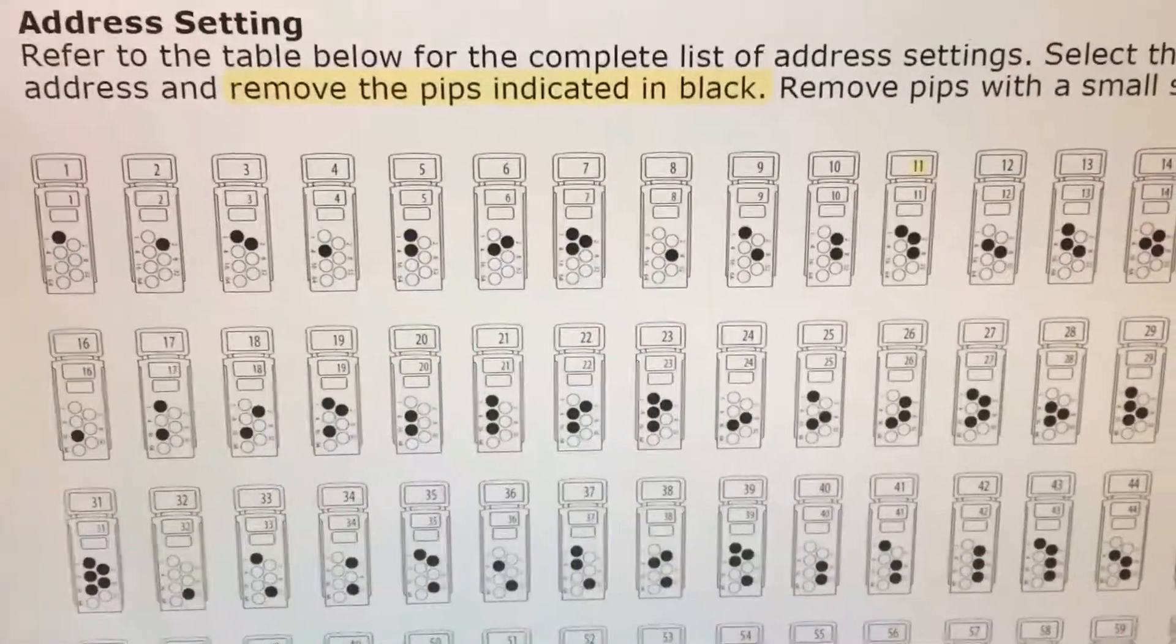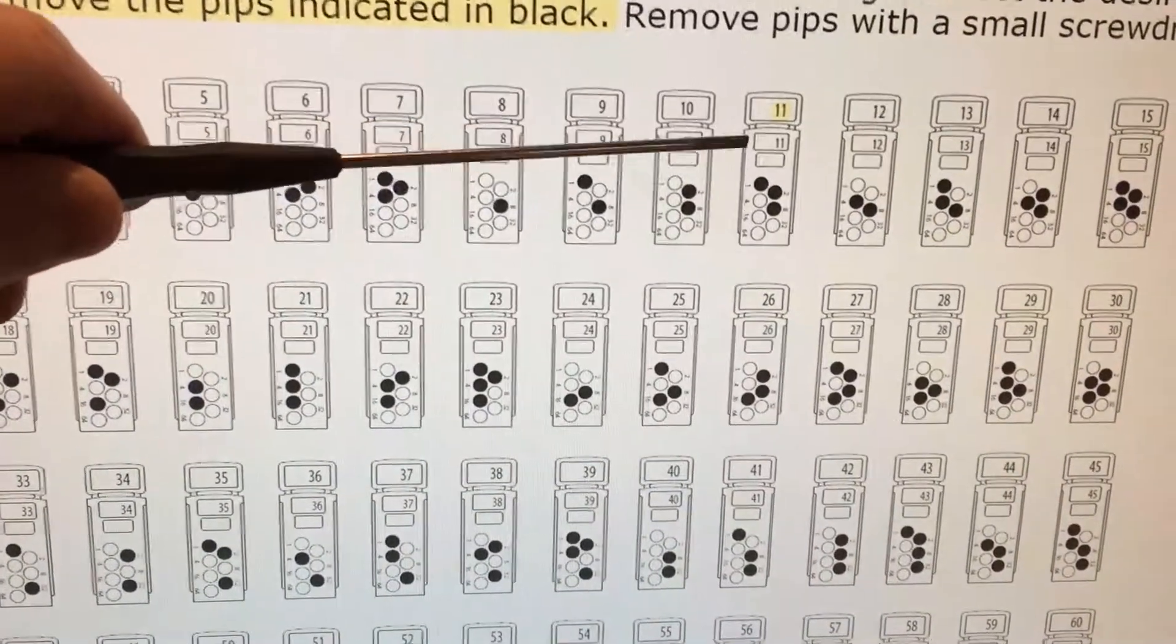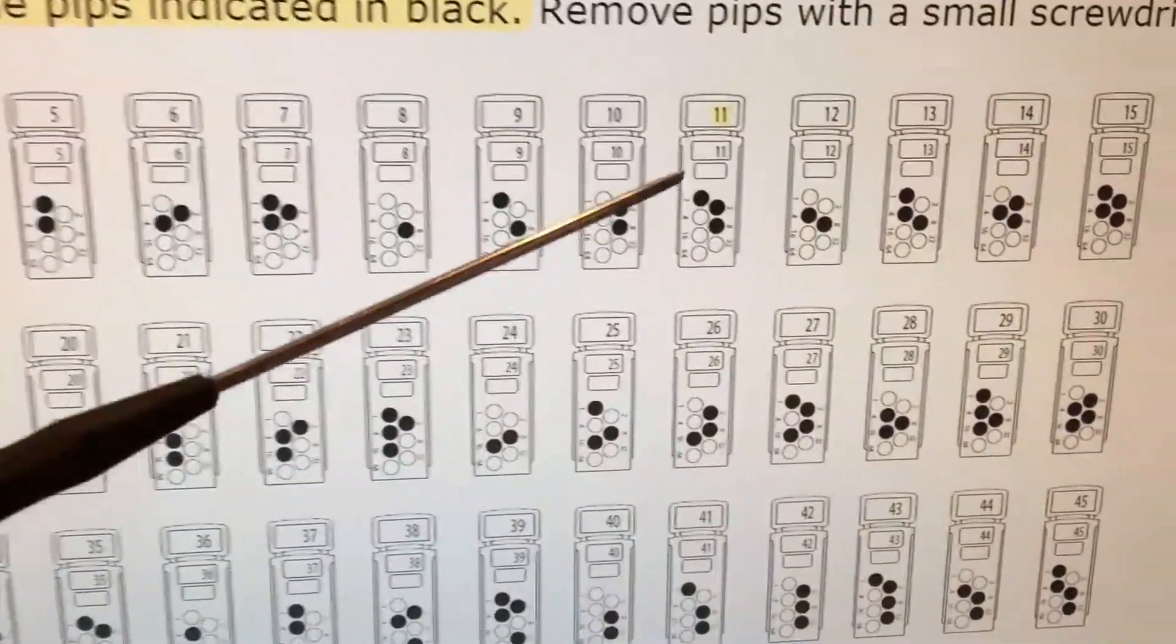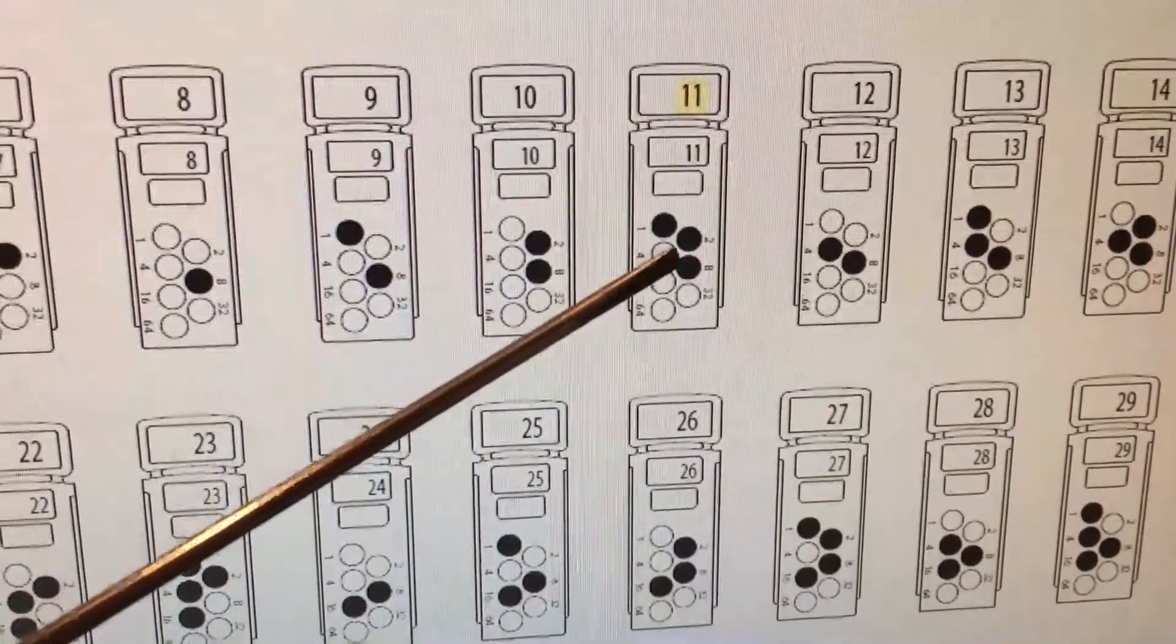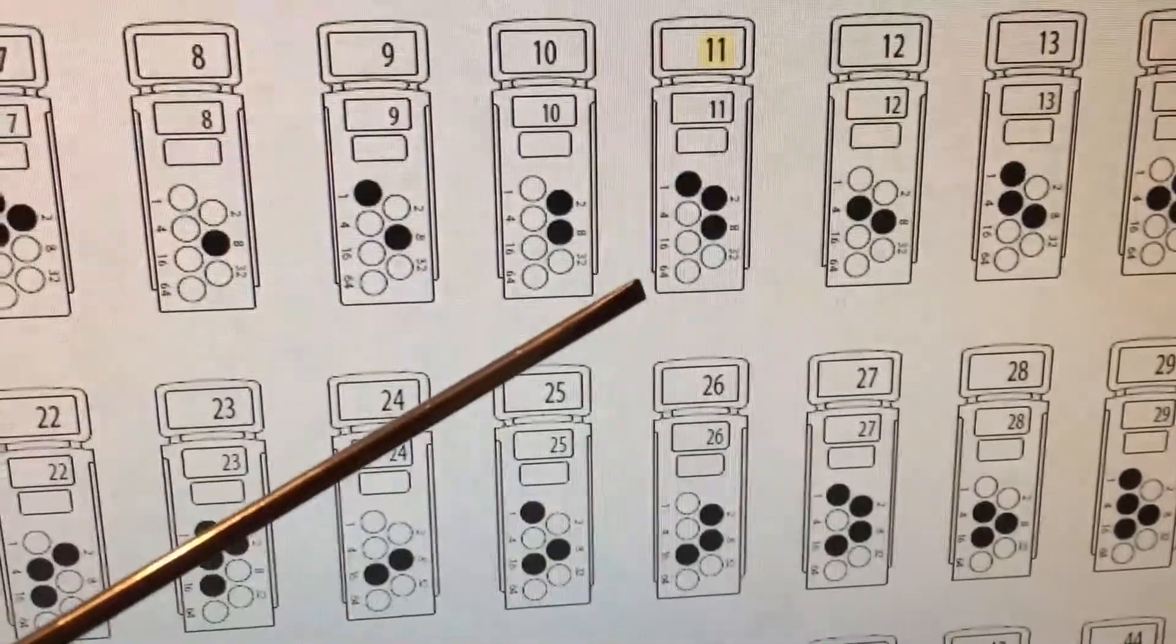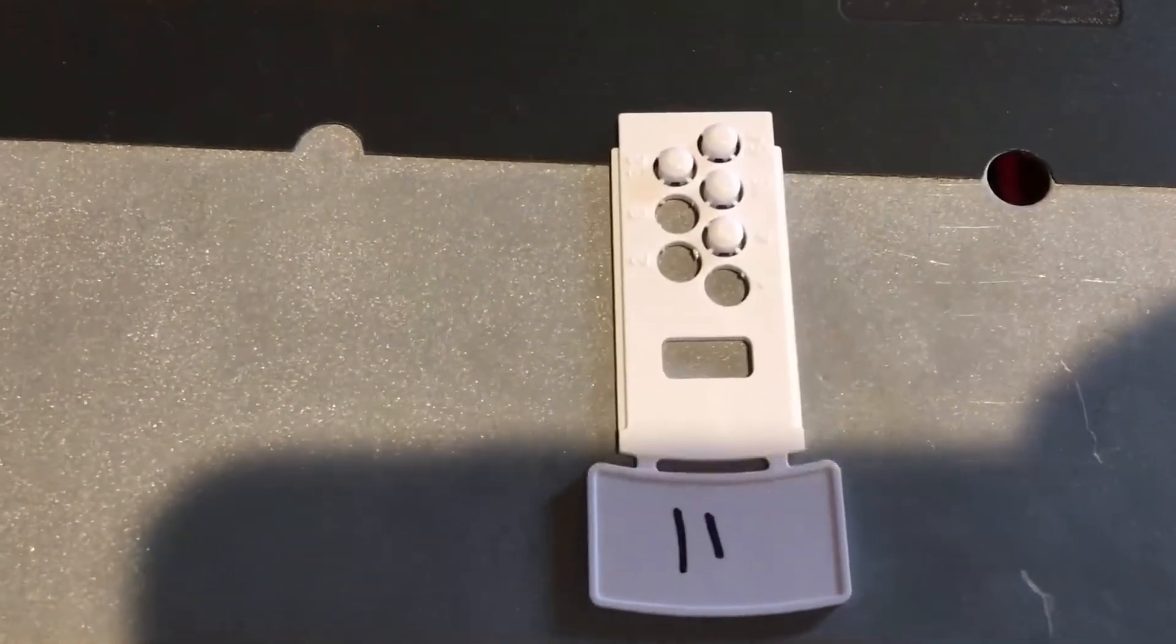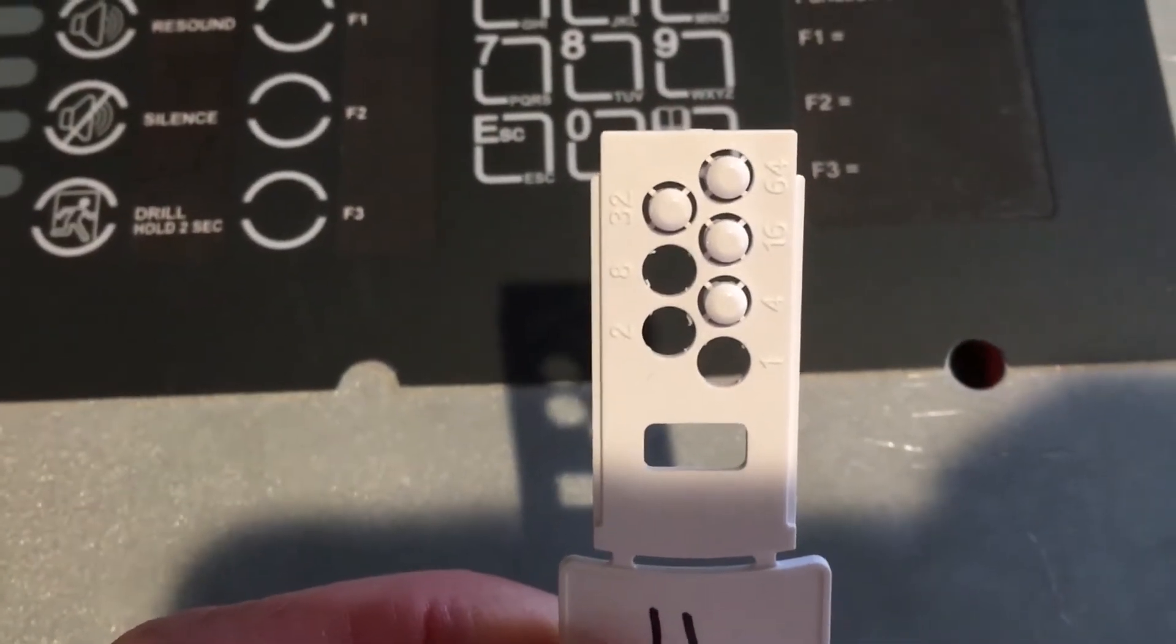Our next item is going to be a smoke detector and that's going to be inserted into a base. You slide out the addressable card and as it says up here, remove the pips indicated in black and that sets the address. This device is going to be address number eleven. Each of these have been marked with numbers and they go from one, two, four, eight, sixteen, thirty two, and sixty four. So to get an address of eleven: eight, two, and one, and that makes eleven. Here is our little label card that we slid out of our smoke detector base and you can see that one, two, and eight have been removed.